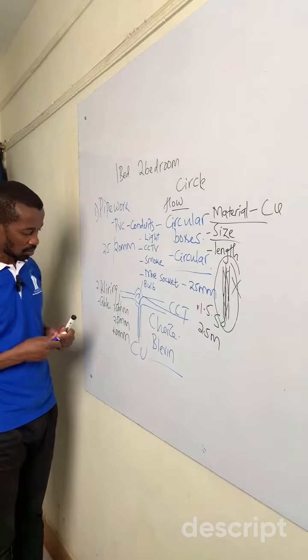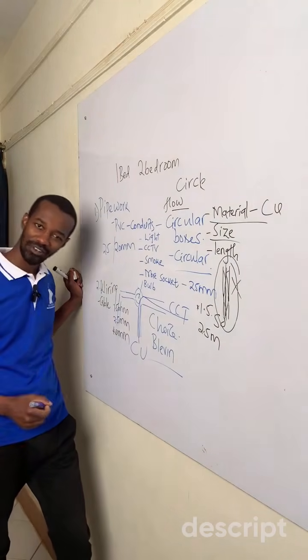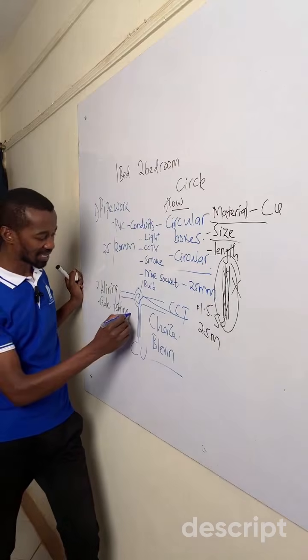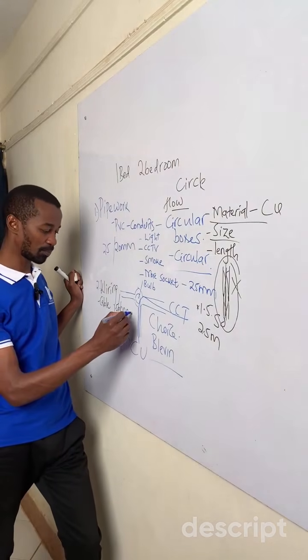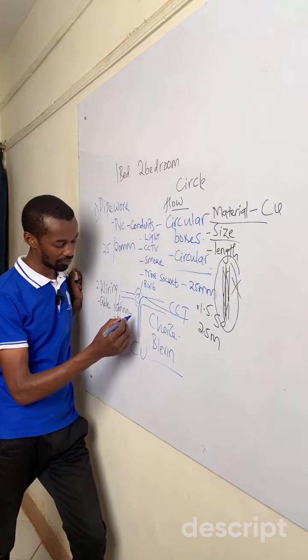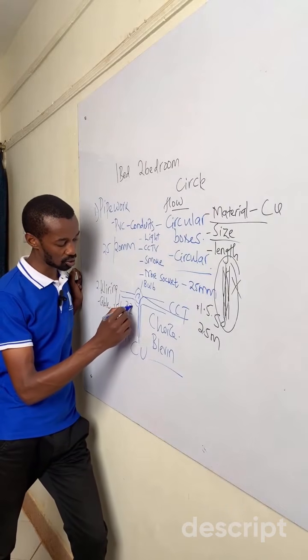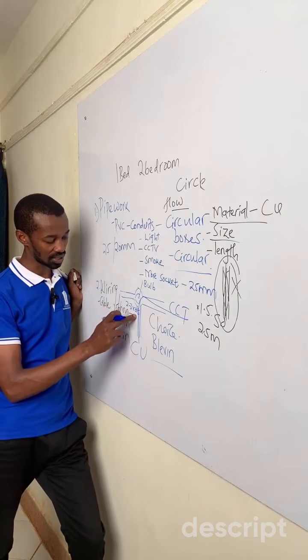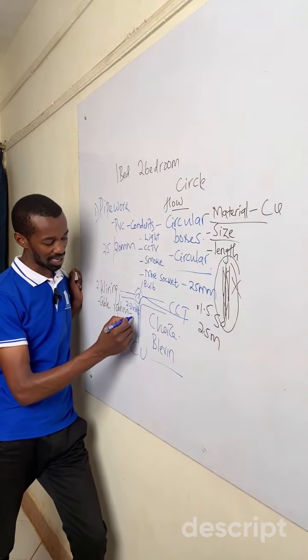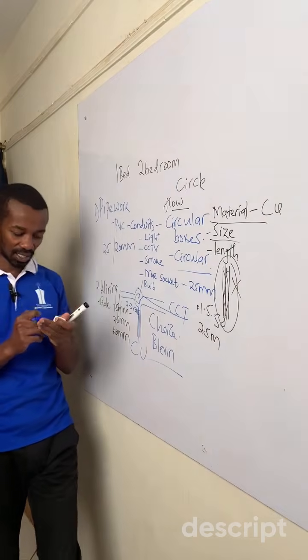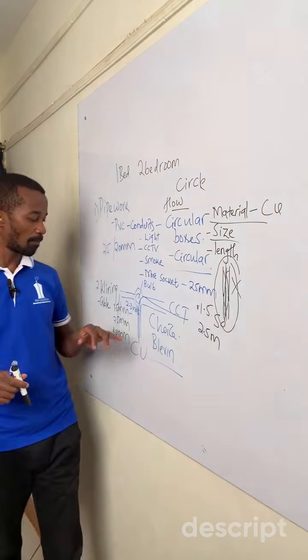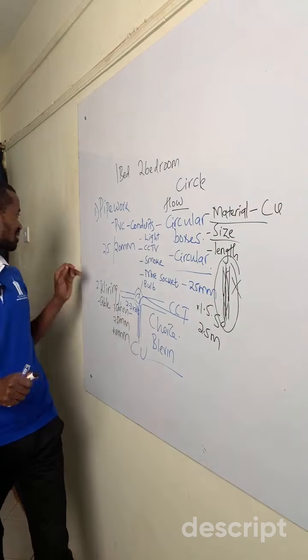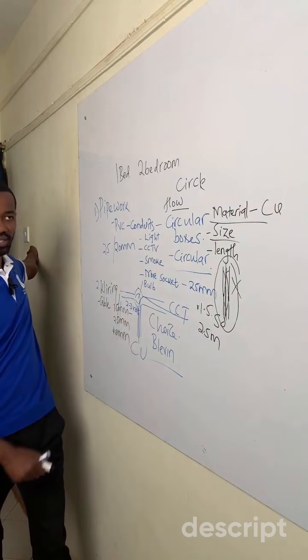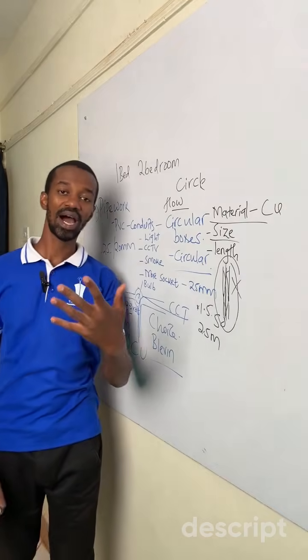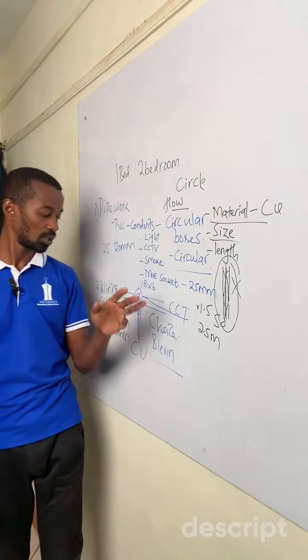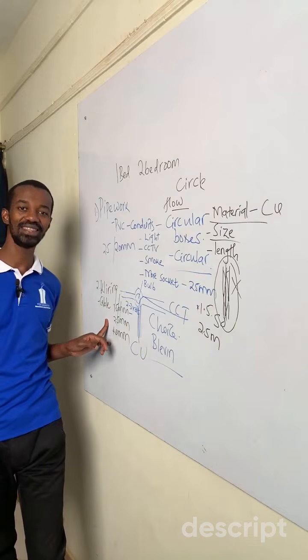Now, my top boss, when it comes to 1.5 cables, this is very interesting. You find that the red cables will be used in plenty. In a 1 bedroom, you may find that you use 2 to 3 rolls. Of course, you might not exhaust the 3 rolls of red cables. And then when it comes to black cables, there are circuits where you will not require the black 1.5 cables. For instance, if you're connecting a two-way switch system, unless you are wiring a smart home. A smart home will require provision of the neutral in the switch.